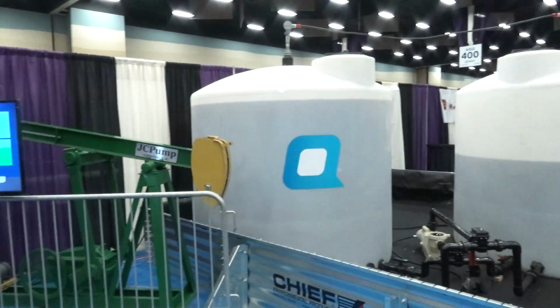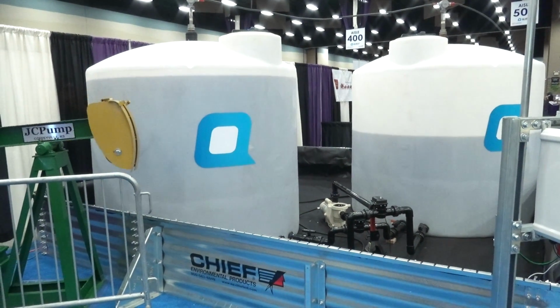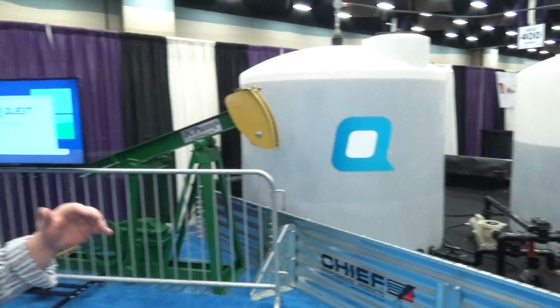With the injector well, if your injector well went out and your pump jacks, these little guys, kept on pumping the water, it would overflow your tanks. So what we're able to do is stay in front of it. Let's just say you're producing a lot of water that day for whatever reason, and your pump jacks are putting in way too much. We can actually shut the pump jacks off for, say, 2 hours, let the injector pump catch up, and then kick the pump jacks back on, and that streamlines your oil production. So you're getting the maximum production out of that site without using timers, without best guess. It is scientific at that point.